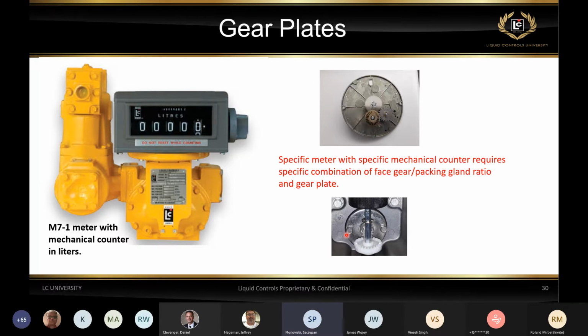It is common, and I see it probably more commonly in the aviation market, that you have possibly 2 meters side by side, 2 meters of different sizes. They both could be measuring liters, they both could be measuring gallons, but they have different gear plates. And I see people just grabbing a counter with its gear plate from one meter and moving it to a different meter of a different size. When that happens and you try to calibrate that meter, you will be far off, depending on what that gear plate is. So again, a specific meter with a specific mechanical counter in specific units of measure will require a specific combination of face gear, packing gland ratio and a gear plate. If you don't have it right, you're never going to be able to calibrate that meter. This combination puts you in the range of adjustment that we can make on a calibrator or adjuster, and then you can do the fine tuning.